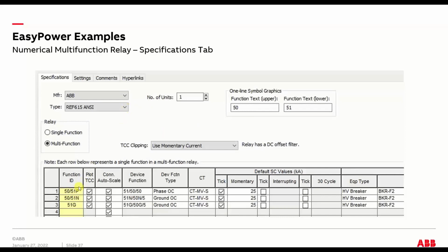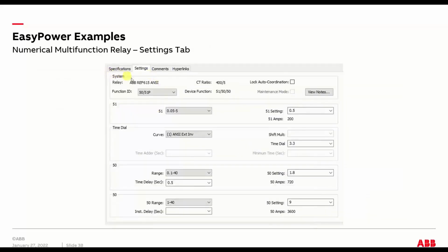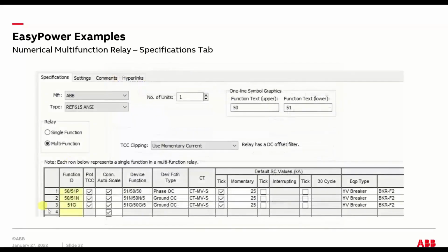Here's your type. This one's multifunction, so you can add in as many functions as you want to have turned on in a relay. So this one's really basic. It's got an instantaneous and time overcurrent phase, same for the neutral, and then a time overcurrent for the ground. And then here's the details, so you have basically four devices in one.